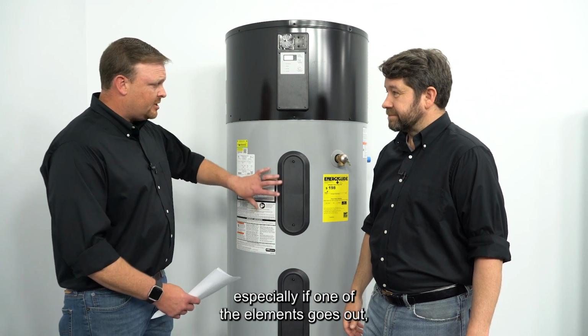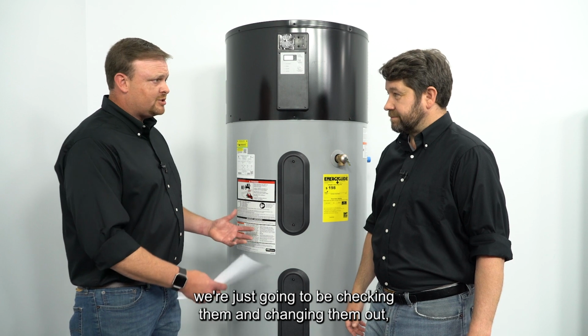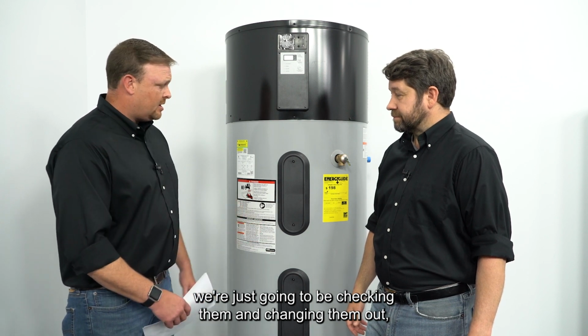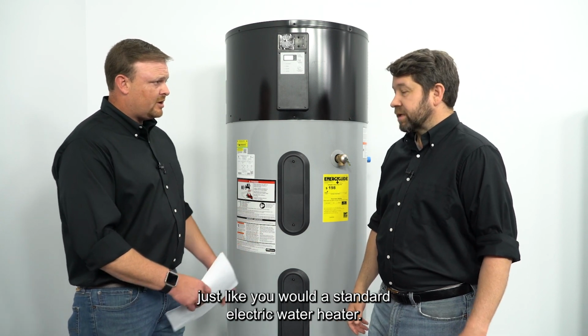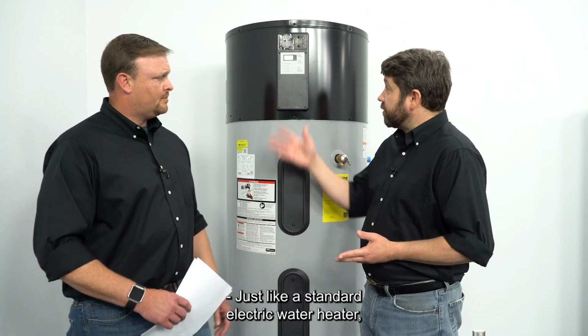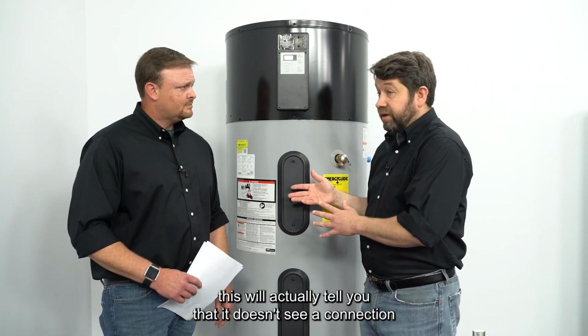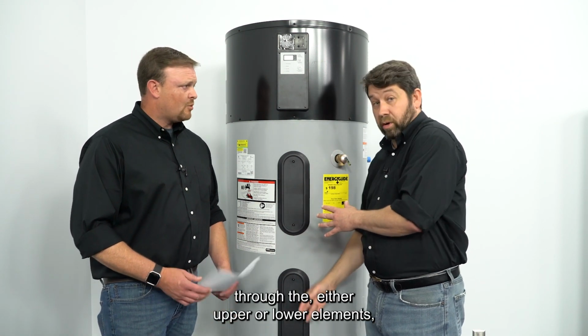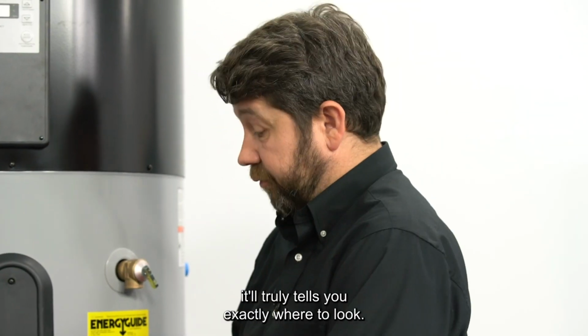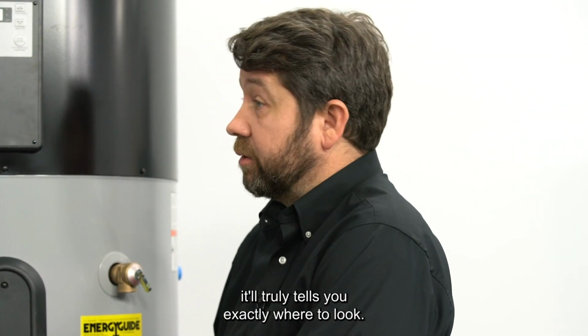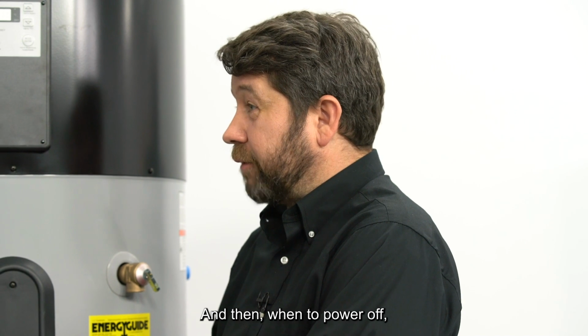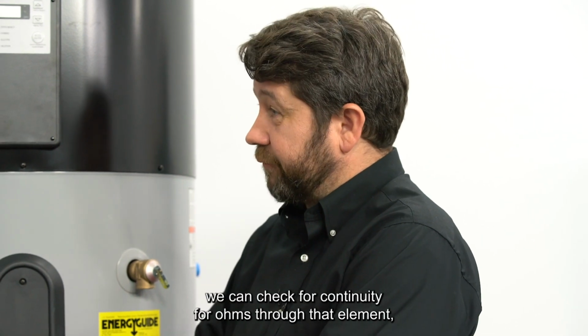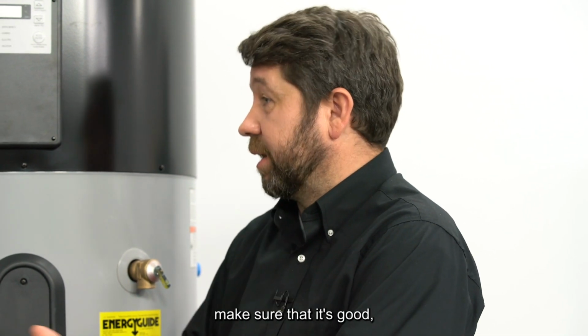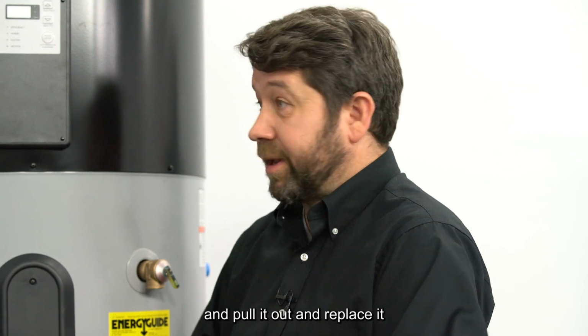And one more thing, with the tank, from here down, it works just like an electric water heater. Especially if one of the elements goes out, we're just going to be checking them and changing them out just like you would a standard electric water heater. Just like a standard electric water heater, this will actually tell you that it doesn't see a connection through either the upper or lower elements. It'll give you that fault, which really tells you exactly where to look. And then when powered off, just like we would with standard electric, we can check for continuity or for ohms through that element, make sure that it's good, and pull it out and replace it.